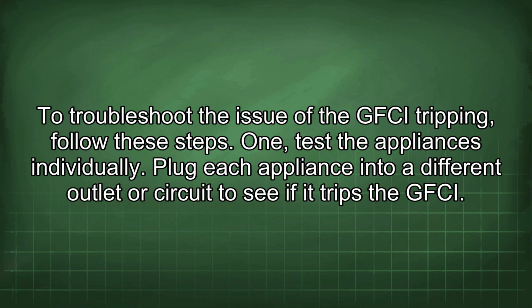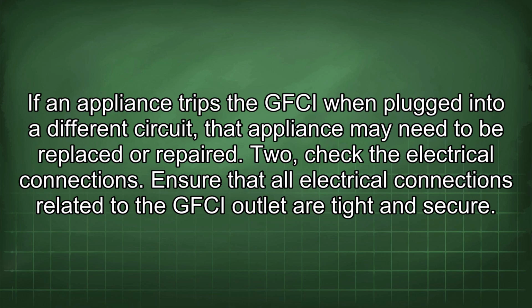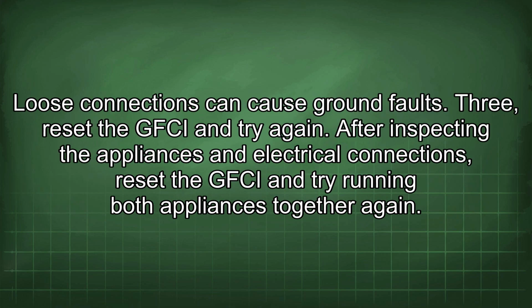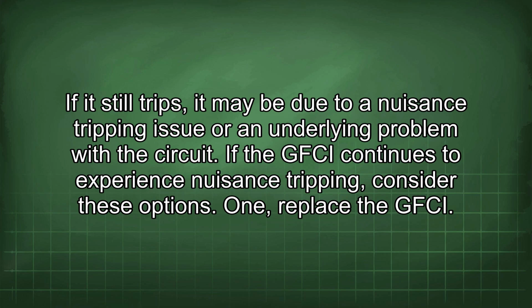To troubleshoot the issue of the GFCI tripping, follow these steps. 1. Test the appliances individually. Plug each appliance into a different outlet or circuit to see if it trips the GFCI. If an appliance trips the GFCI when plugged into a different circuit, that appliance may need to be replaced or repaired. 2. Check the electrical connections. Ensure that all electrical connections related to the GFCI outlet are tight and secure. Loose connections can cause ground faults. 3. Reset the GFCI and try again. After inspecting the appliances and electrical connections, reset the GFCI and try running both appliances together again. If it still trips, it may be due to a nuisance tripping issue or an underlying problem with the circuit.